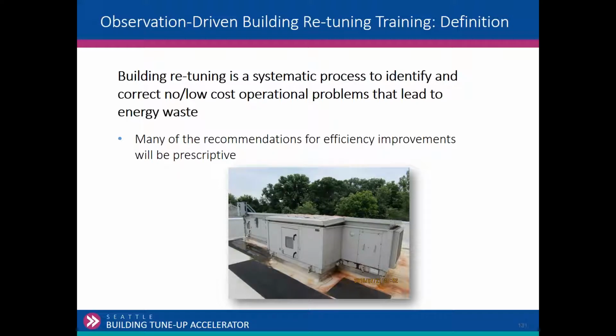So that's on the BAS side. On the BAS side, you're looking at a graphic screen and you're getting feedback. I will caution you that a lot of what you see on a graphic screen is the commanded value, not the actual value. So it's a little bit of trust but verify, at least for some of that. On the smaller package rooftop units, with no BAS, it's going to be physical observation. If you've got 10 package rooftop units, you're required to tune up 10 package rooftop units. So it's really going to be through data logging and the physical observations on what you can identify in those systems.